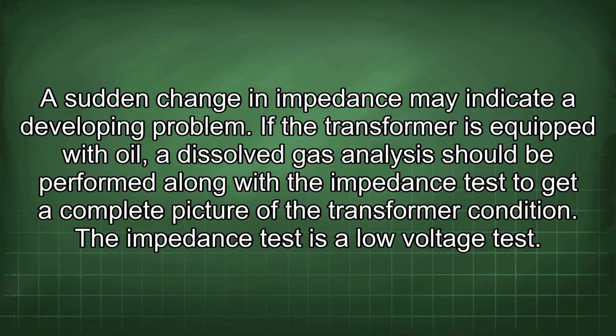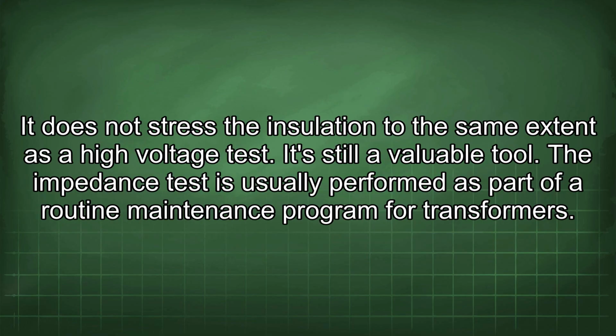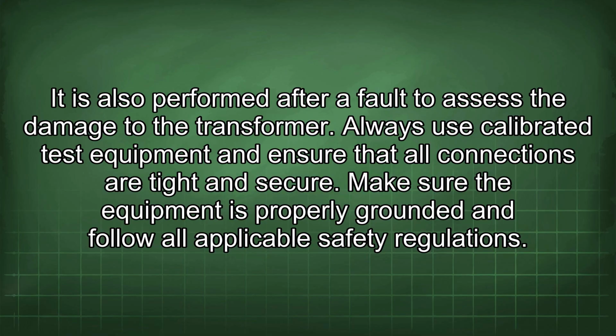If the transformer is equipped with oil, a dissolved gas analysis should be performed along with the impedance test to get a complete picture of the transformer condition. The impedance test is a low-voltage test. It does not stress the insulation to the same extent as a high-voltage test. It's still a valuable tool. The impedance test is usually performed as part of a routine maintenance program for transformers. It is also performed after a fault to assess the damage to the transformer.